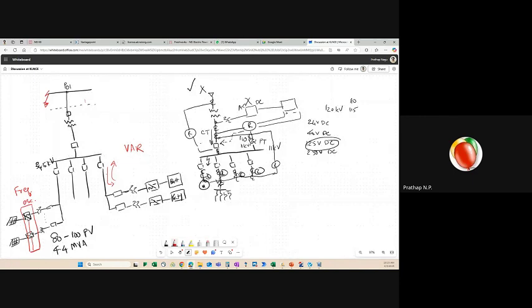So there's no actual energy conversion happening here. It is just taking power from the grid and sending it back as VAR, except there will be some losses in the transformer impedances and cable impedances here, but that's fine. Now batteries can act as a VAR source at nighttime whenever it is needed. That is because all these inverters talk to each other. They form one giant source, and they can put that out.